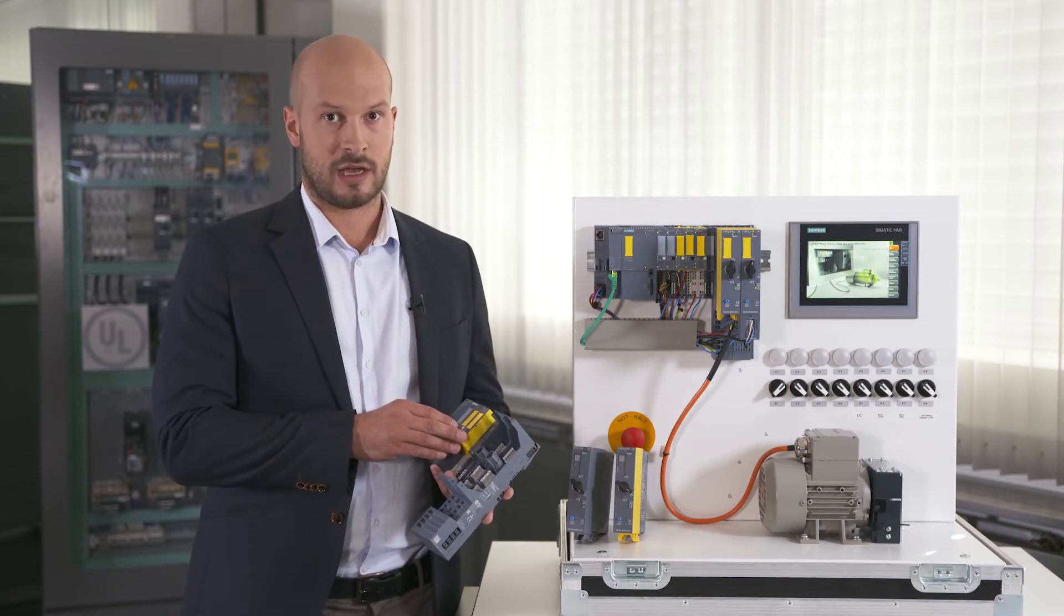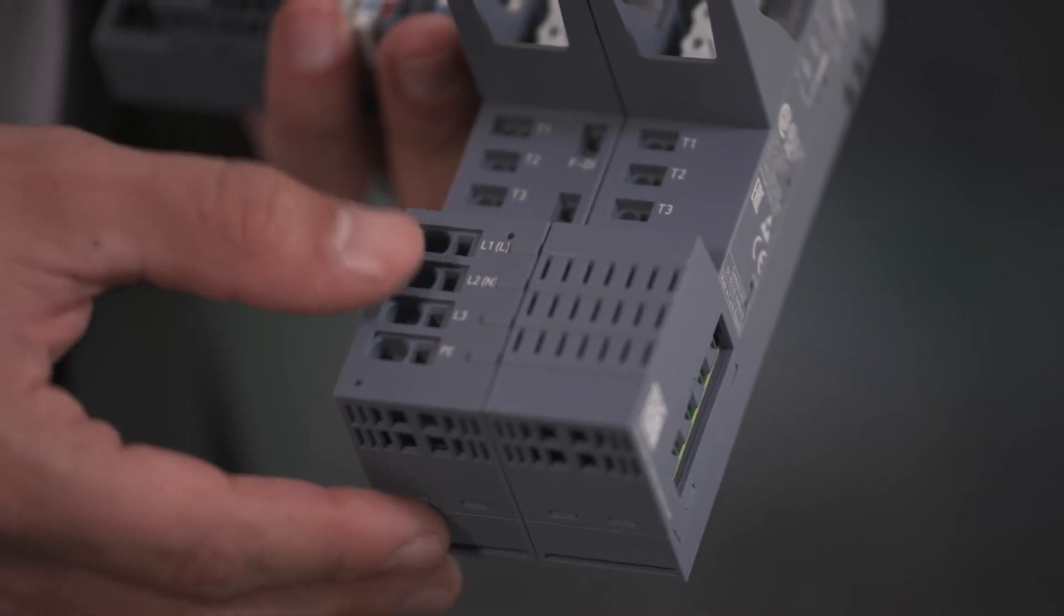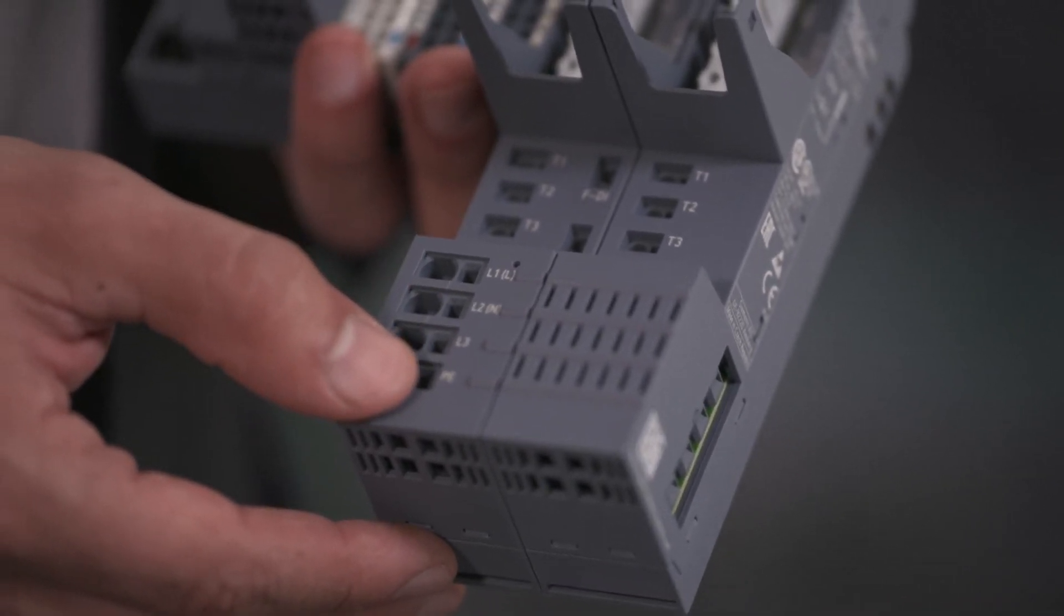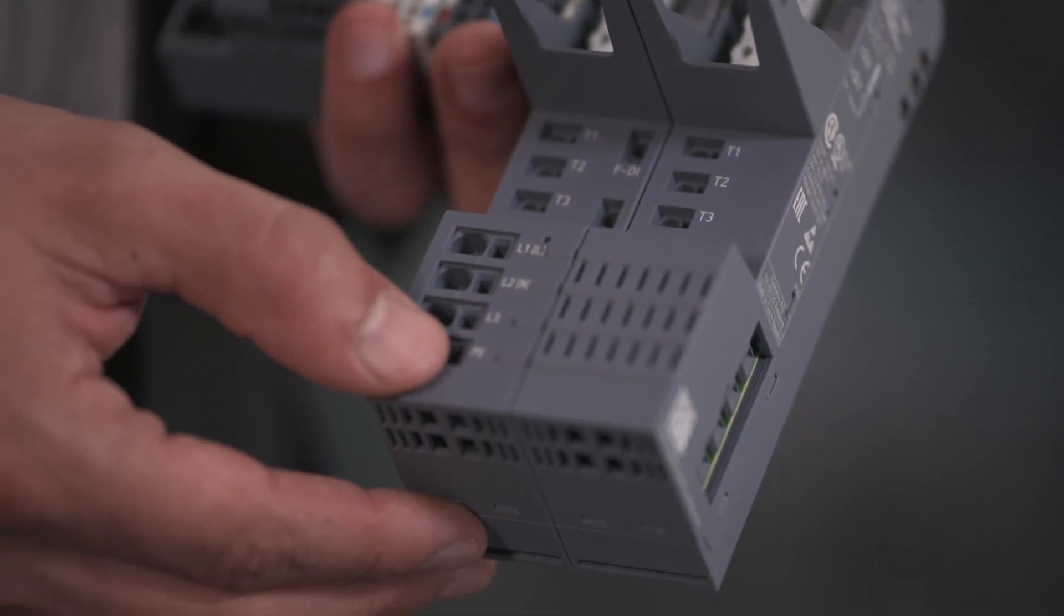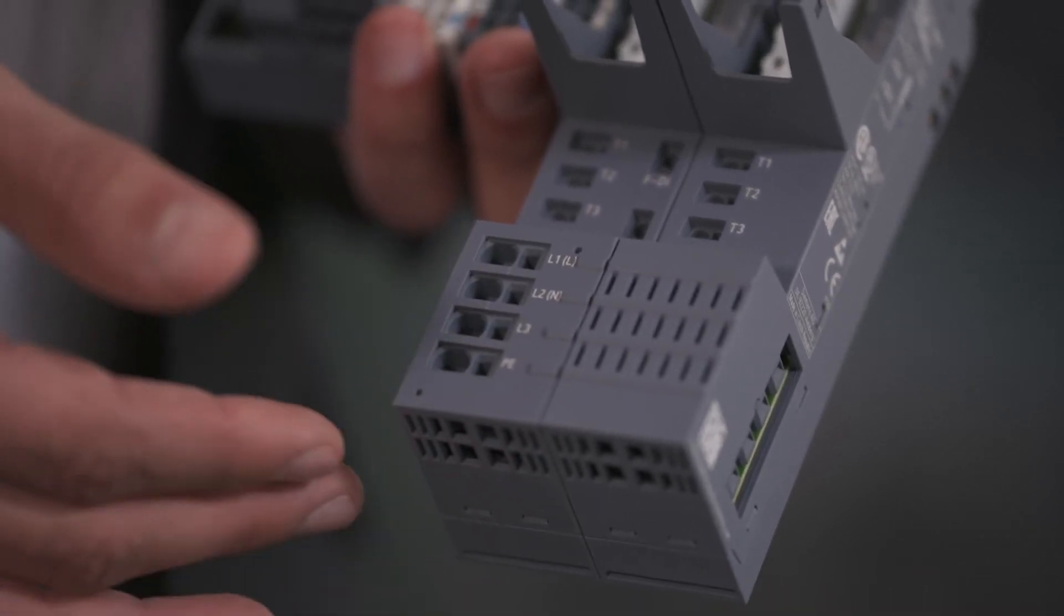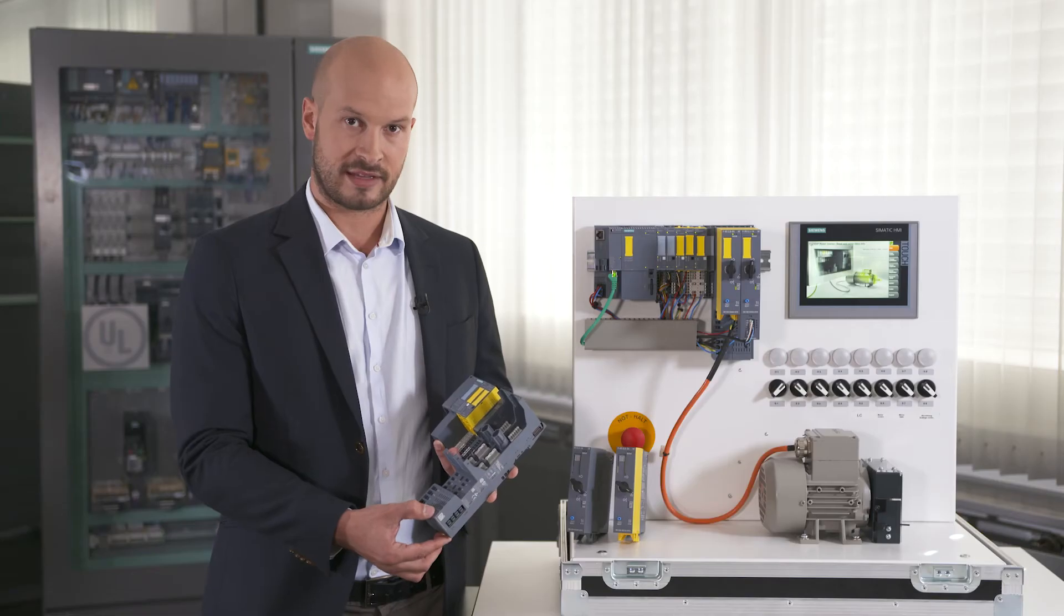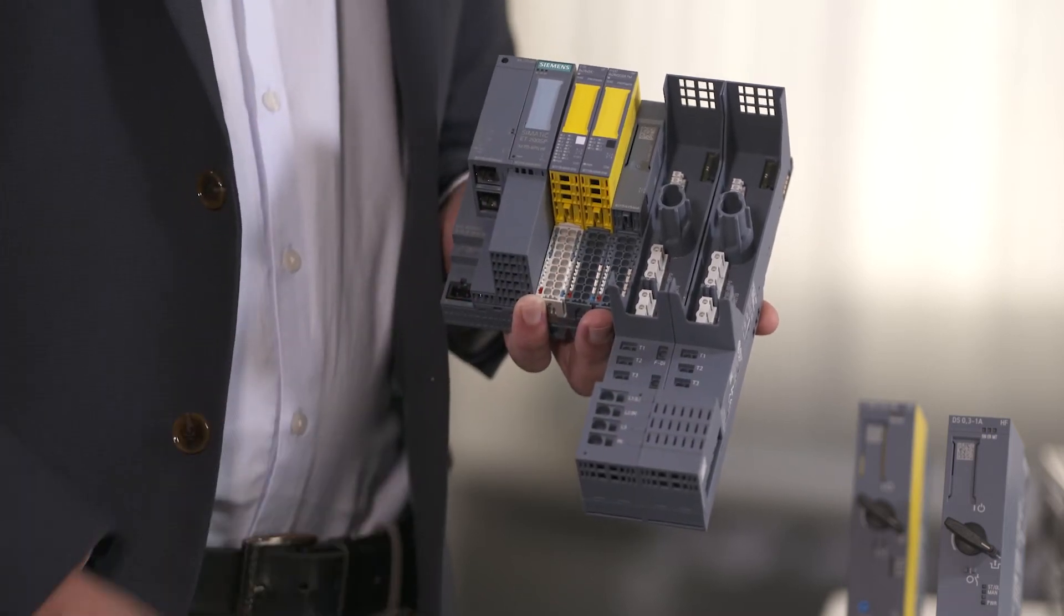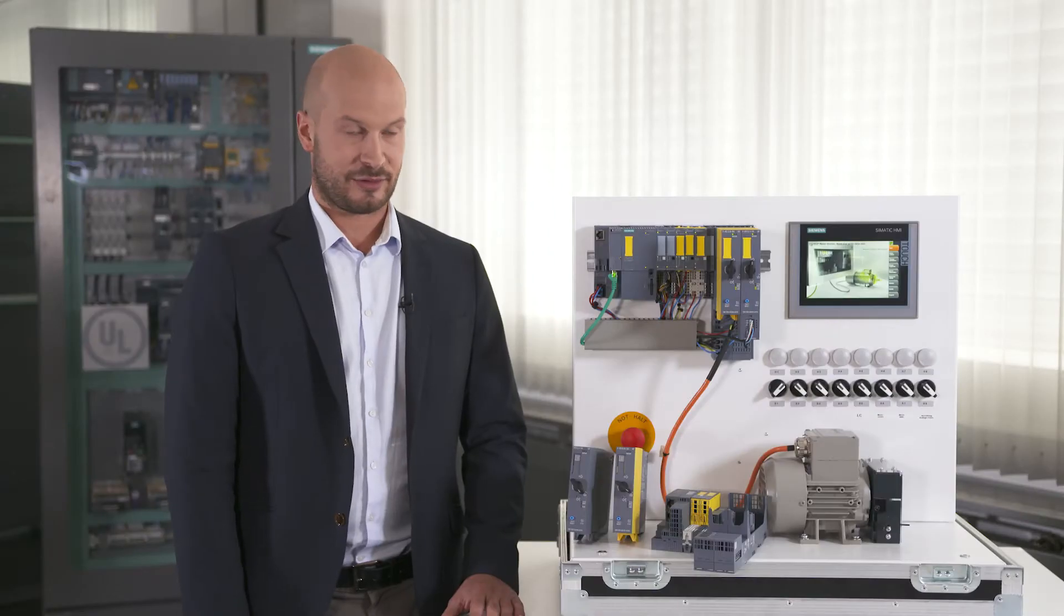Another advantage is that we also have an energy bus for the main voltage and supply voltage. You can see it down here on the motor starter base unit. I only have to feed in the voltage at the first module, the main voltage, and then it is forwarded to the other modules via the base units. I then only have to wire this motor feeder at the top here.